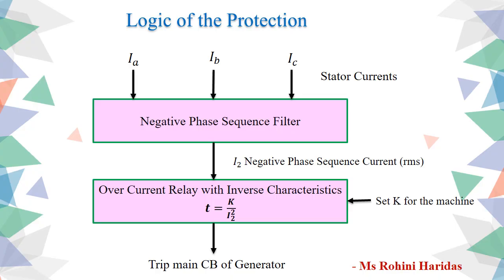The protection against unbalanced loading is provided with the help of an inverse time over-current relay, which is fed with the negative sequence component of the stator current. To extract the negative sequence component of the stator current, we use a negative phase sequence filter. Under normal operating conditions, there is no negative phase sequence component in the stator current, so the filter produces no output and the relay is inoperative. When an unbalanced load occurs, the negative phase sequence filter produces an output proportional to the negative phase sequence component, which is given to the relay coil, causing the relay to operate and open the circuit breaker to isolate the generator.